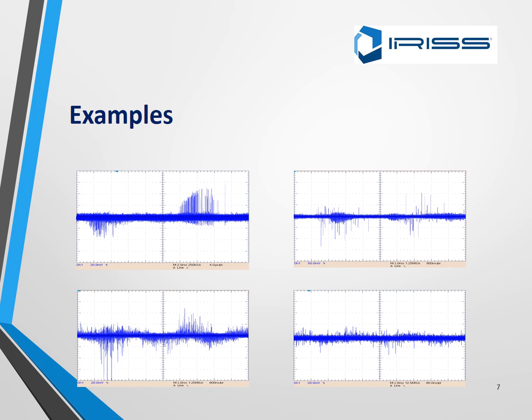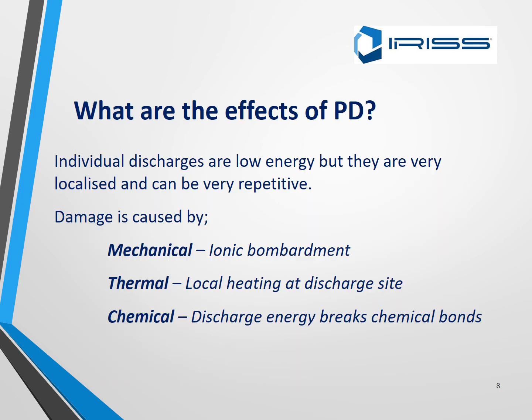What are the effects of PD? The individual discharges are low energy but they are very localized and can be very repetitive. Damage is caused mechanically via ionic bombardment, thermally through local heating at a discharge site, and chemically where discharge energy breaks down chemical bonds. Corona or PD is very destructive.